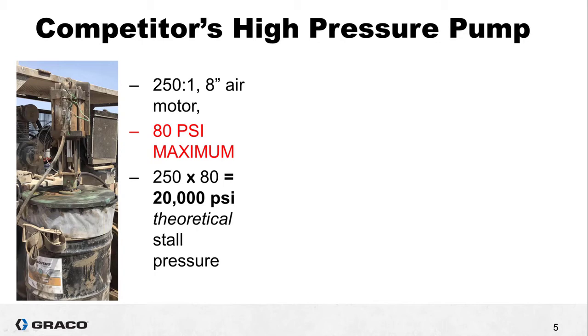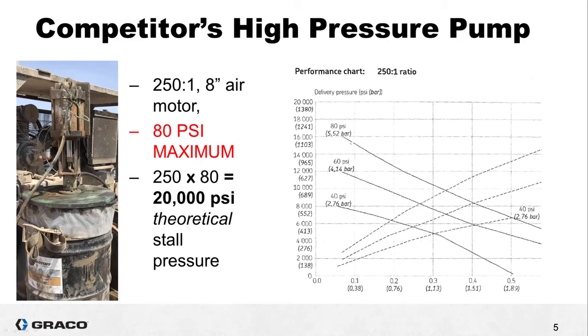Since they state their ratio as 250 to 1 and the maximum air pressure is 80 psi we should be able to multiply 250 times 80 and get the stall pressure. 250 times 80 equals 20,000 psi which is the theoretical stall pressure. But theory is one thing and the real world is another. In the real world our competitors pump stalls at around 18,500 psi in one direction and only 16,000 psi in the other.